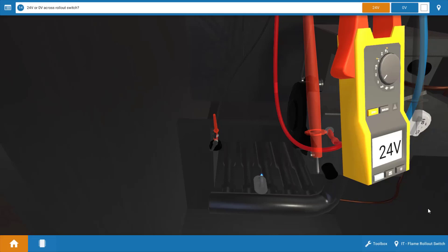But for this instance, we're going to assume that we've checked those and they're all good and that the rollout switch is in fact faulty. So now that we've got 24 volts across the rollout switch, we can click on that.